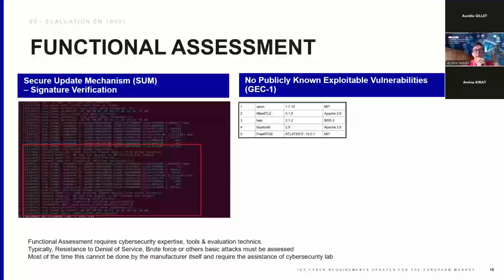Here it is needed to check what the known vulnerabilities are based on the software of the product, and whether these vulnerabilities have indeed been fixed by using the latest software version, or mitigated in case they cannot be fixed, or if the latest versions are not used. So basically, for each identified potential vulnerability based on the software, the idea is to check that it is mitigated enough. It cannot be done without tools, and also by checking concretely that the exploitability is not possible. So here, for example, there is a first level of penetration test, which is done by the lab in order to check that the vulnerabilities are not exploitable.